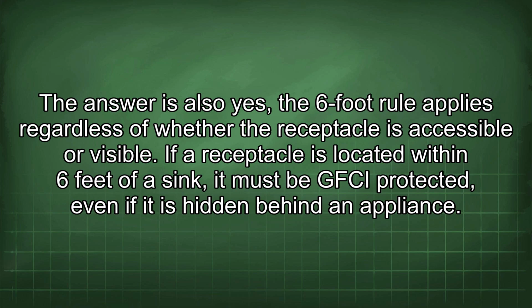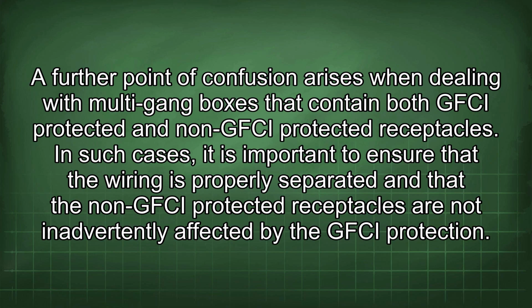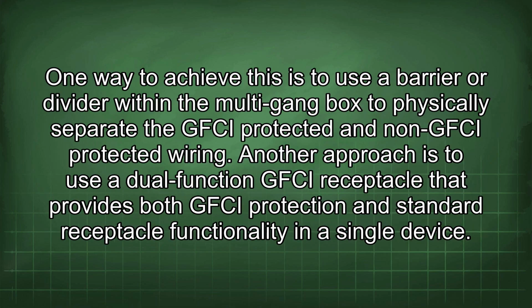hidden behind an appliance. A further point of confusion arises when dealing with multi-gang boxes that contain both GFCI protected and non-GFCI protected receptacles. In such cases, it is important to ensure that the wiring is properly separated and that the non-GFCI protected receptacles are not inadvertently affected by the GFCI protection. One way to achieve this is to use a barrier or divider within the multi-gang box to physically separate the GFCI protected and non-GFCI protected wiring.